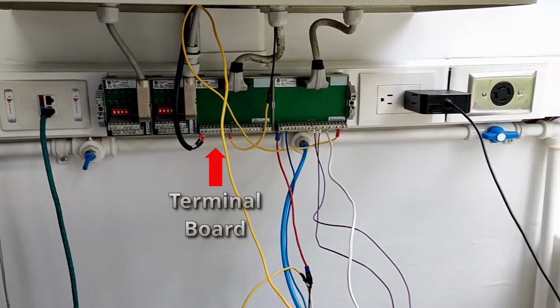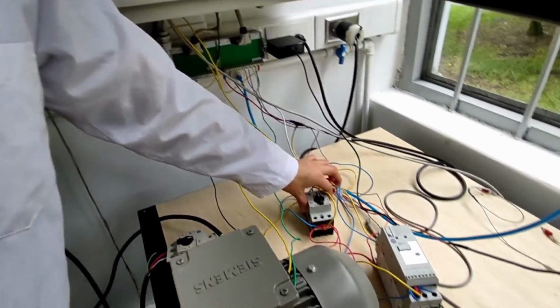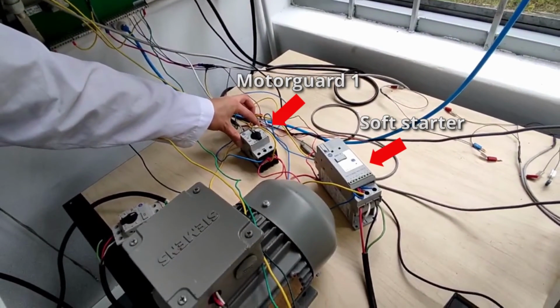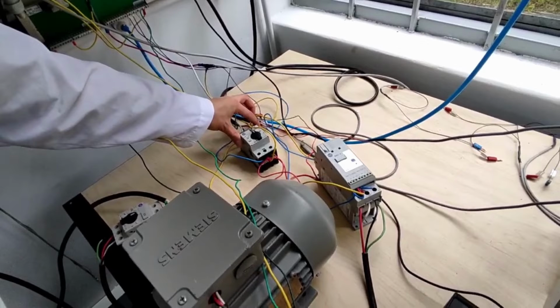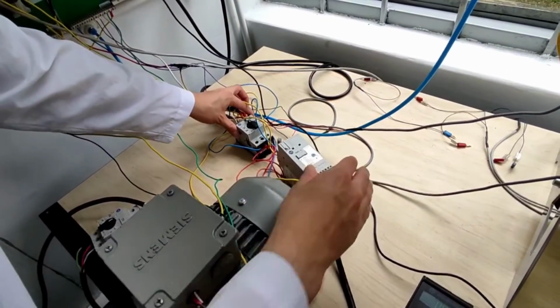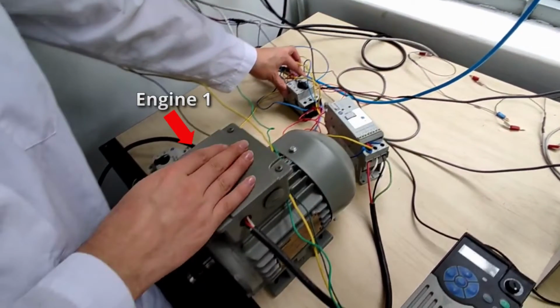In the first place, and related to our above conveyor, we have the engine system, which is composed of the magnetic starter that protects the engine from current overloads, the soft starter that protects the engine from damage caused by sudden influxes of power by limiting the inrush current associated with the engine startup, and our 1 horsepower Siemens engine.